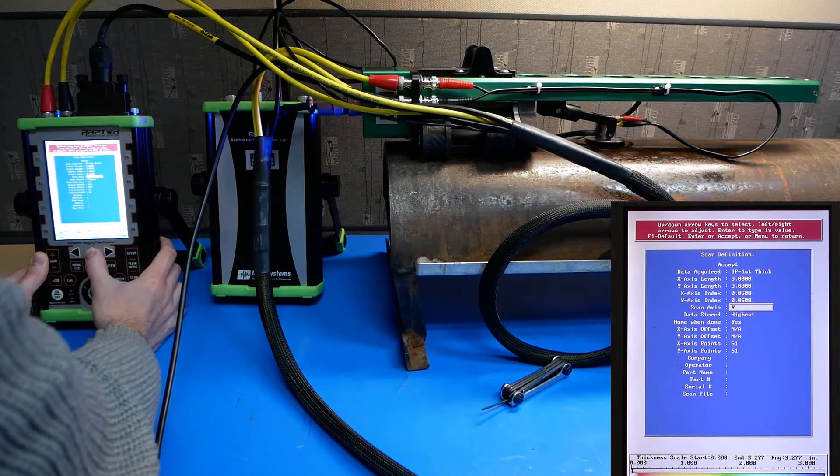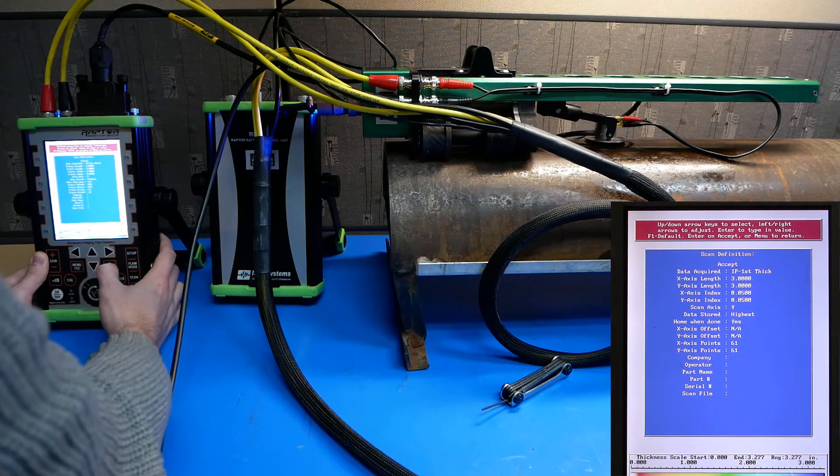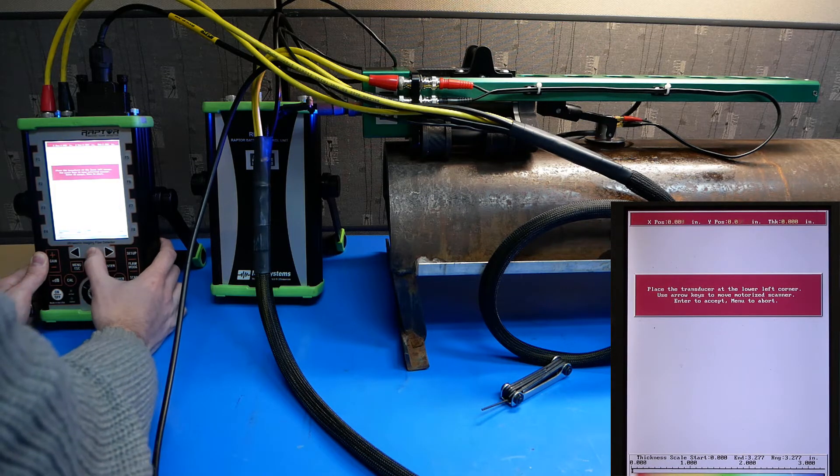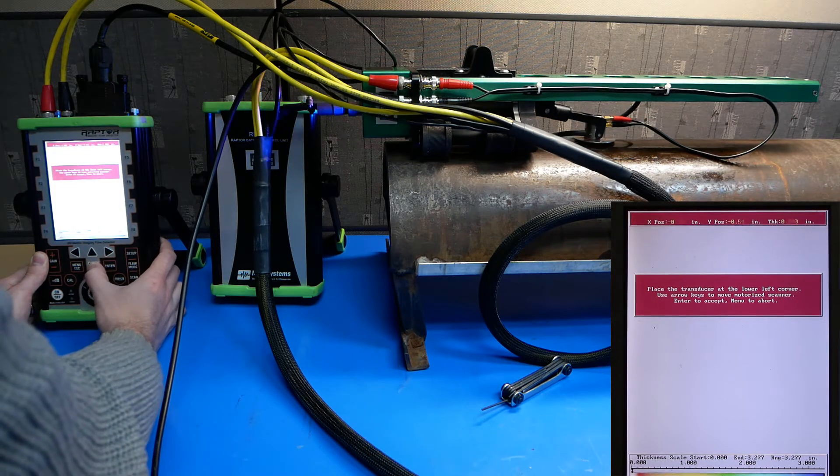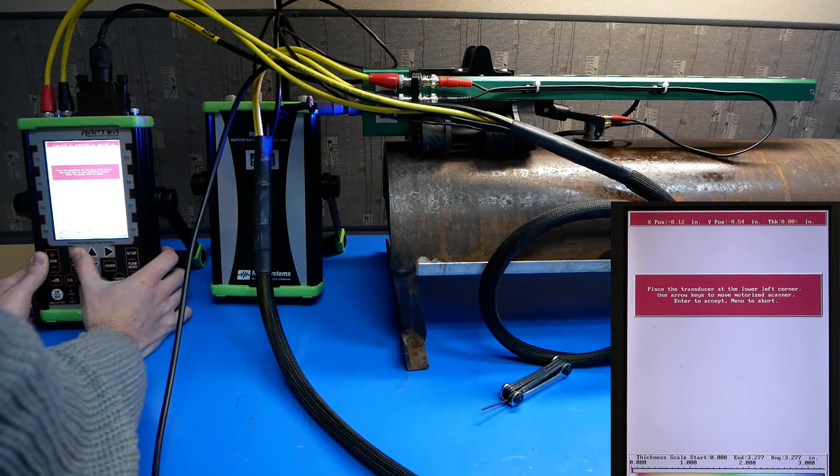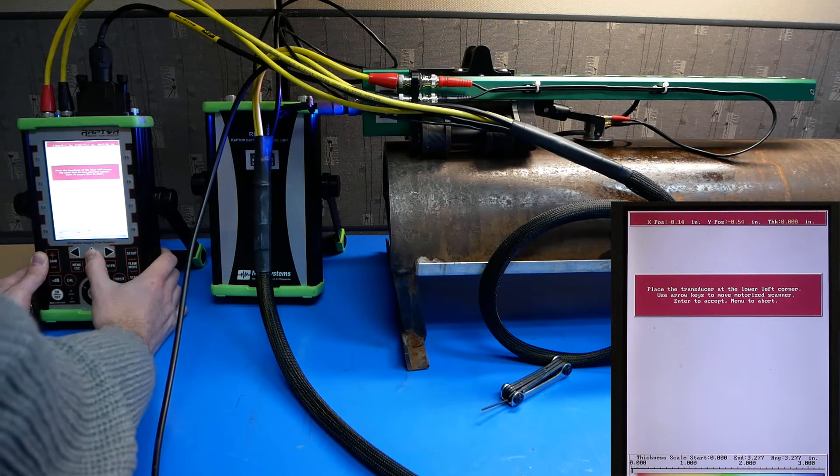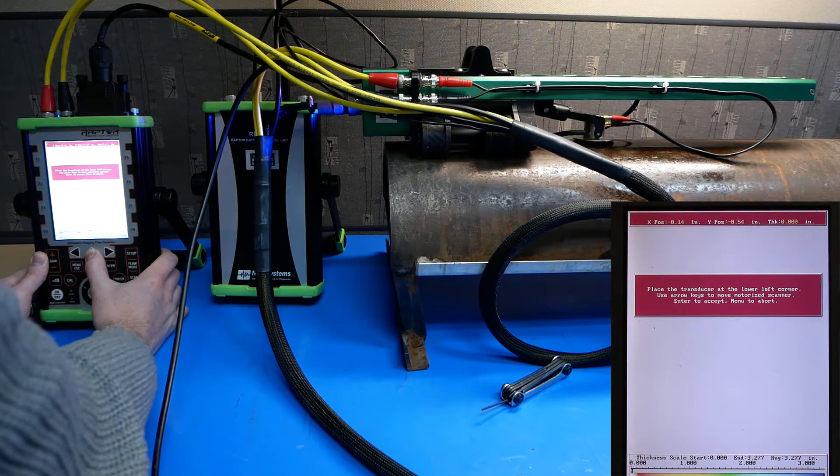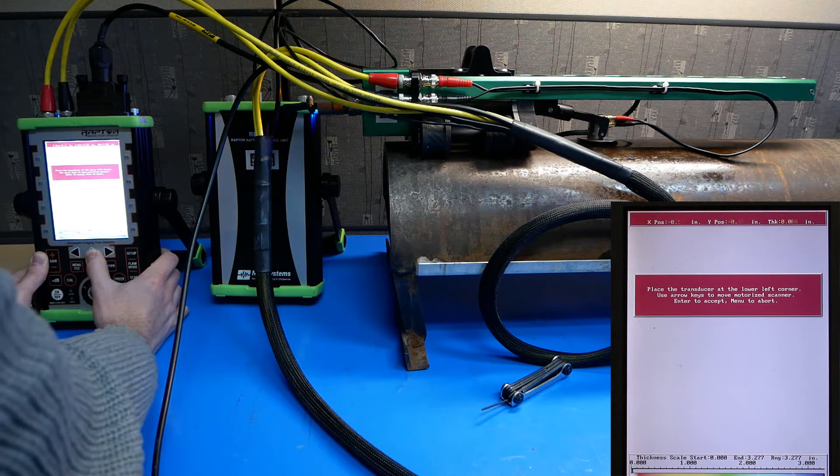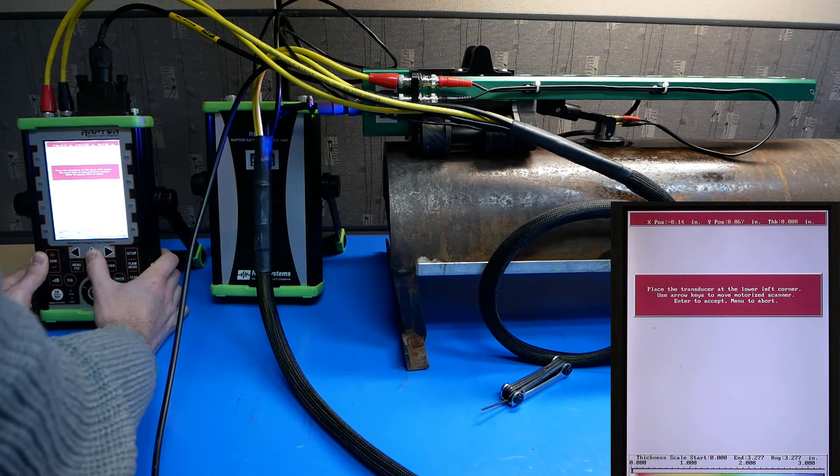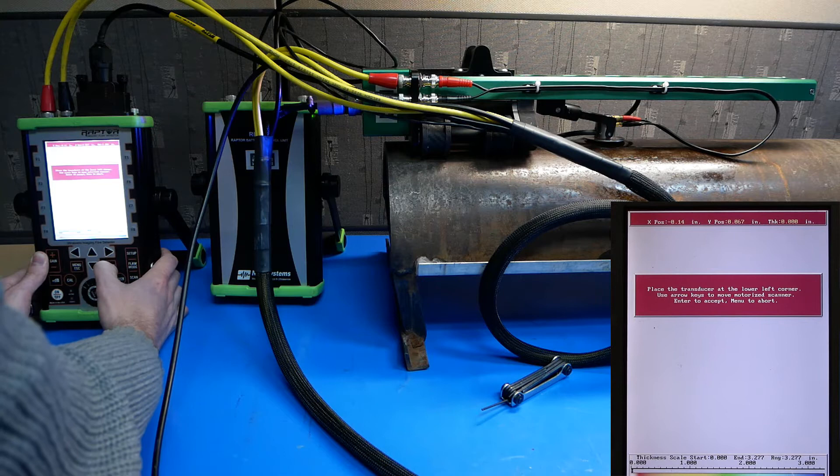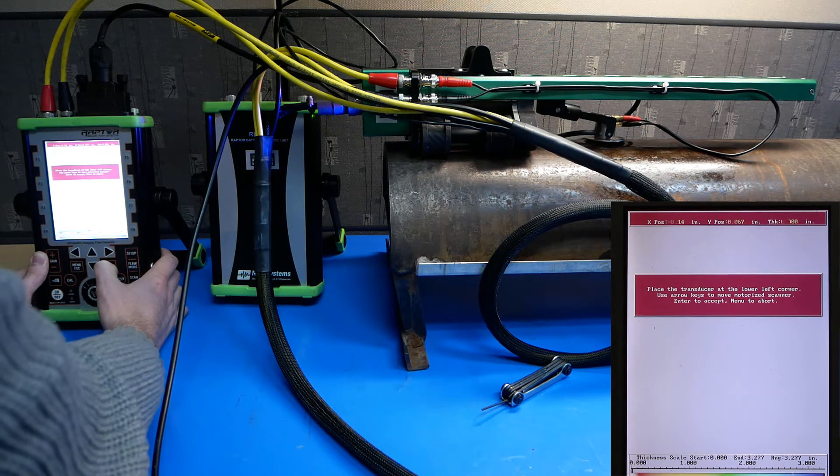And when I'm ready, I'll hit accept. I'll move the transducer all the way back and over a little bit. Once I've done that, I'll offset the transducer a little bit from the edge of the travel and hit enter. This will be my home position.